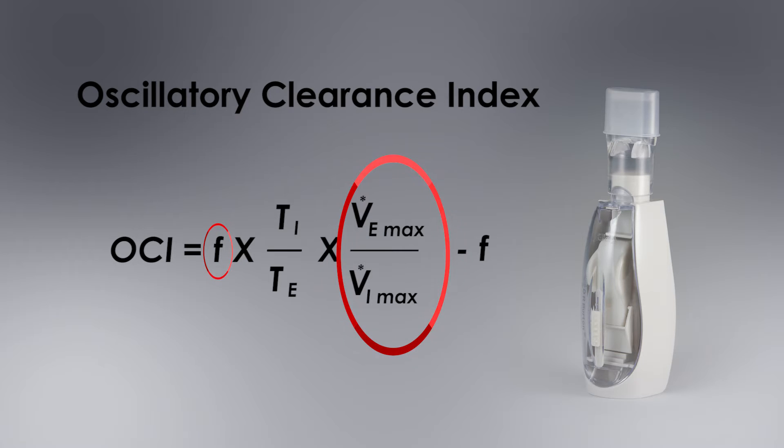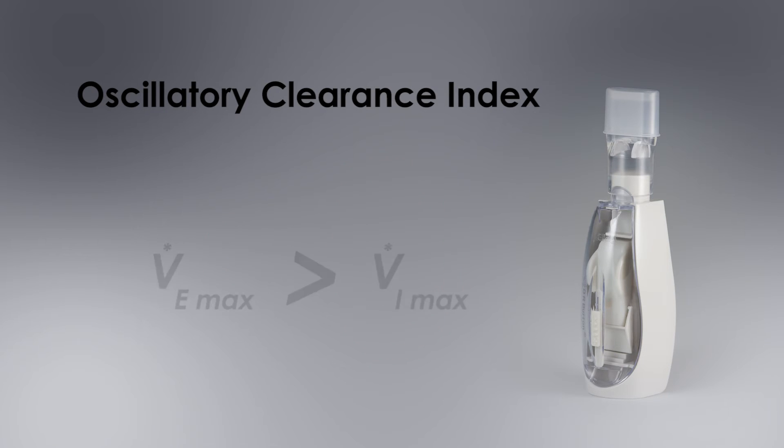To ensure that secretions flow cephalad towards the patient's head, expiratory flow rate must exceed inspiratory flow rate.